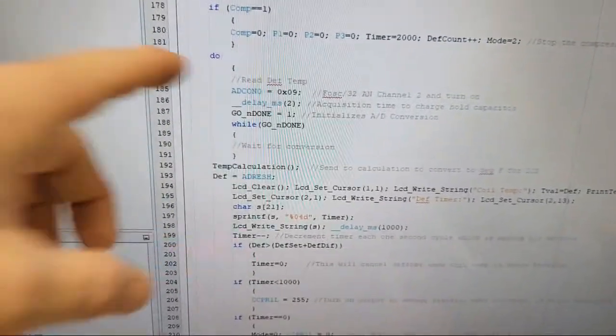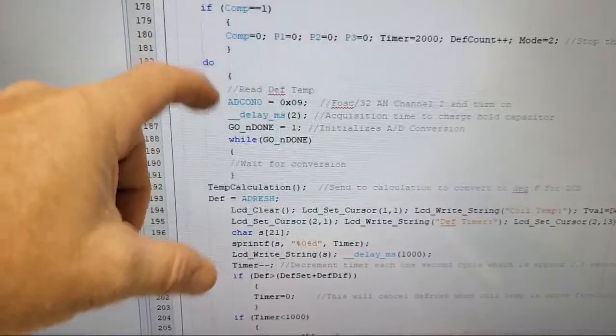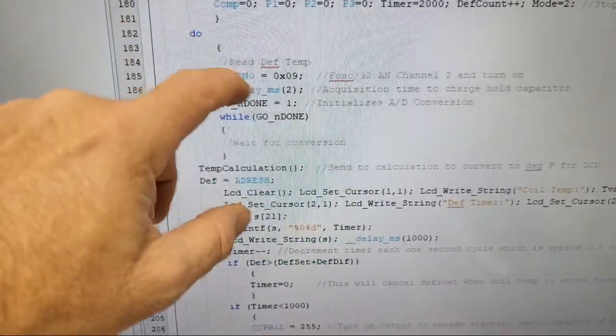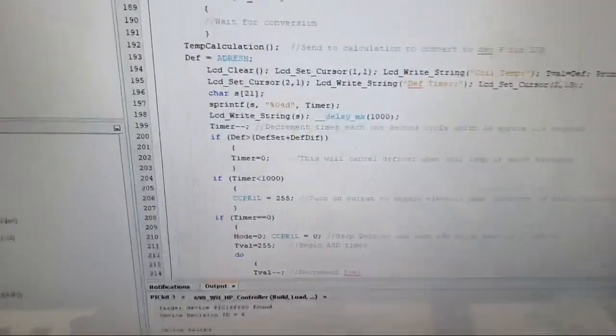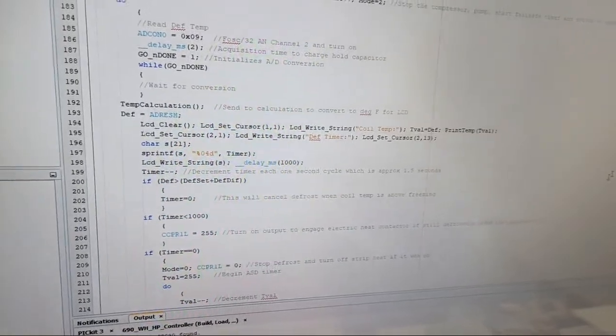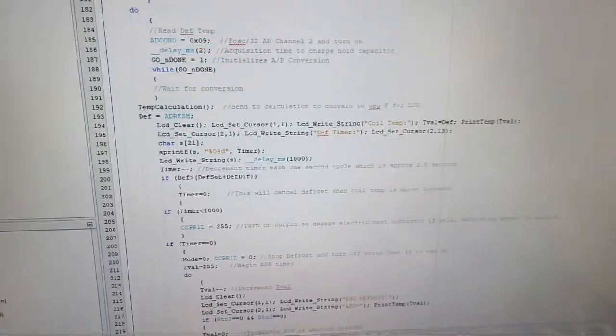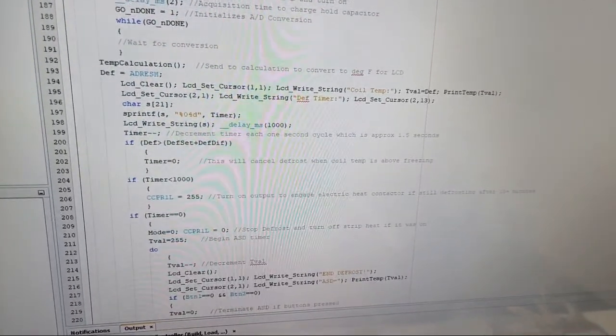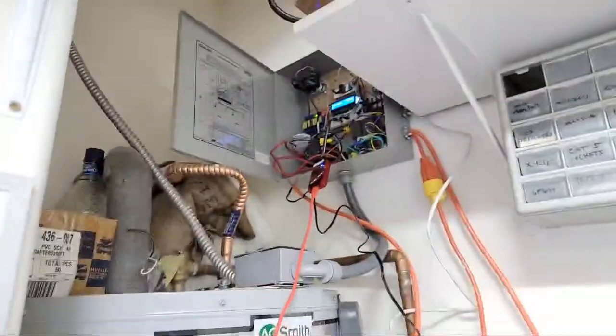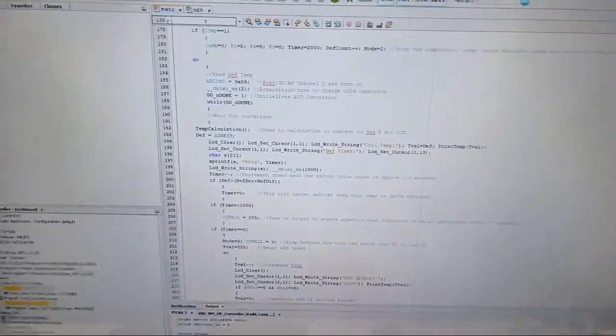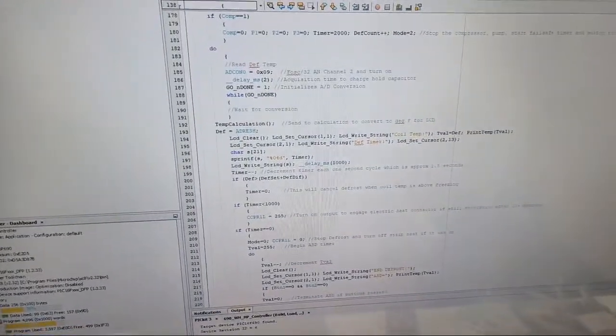And when it goes into defrost, then it's in mode 2 for defrost. It stays there until it terminates. You basically have it keeps coming back to the subroutine because it's in this mode. It'll defrost it, keeps reading that thermistor and counting down the timer. And then a cool thing I did is, if it's more than 15, 20 minutes in defrost and the thermistor hasn't hit the termination point of like 32, 33 degrees, then it's going to turn on this other output, which is a contactor down here. And that contactor right there just gives power to the heat strips. So I don't have to manually switch my system over when it's too cold outside to heat worth a darn. It's gonna turn on electric elements in that thing.